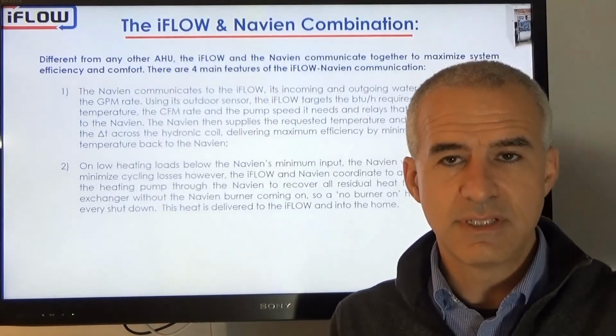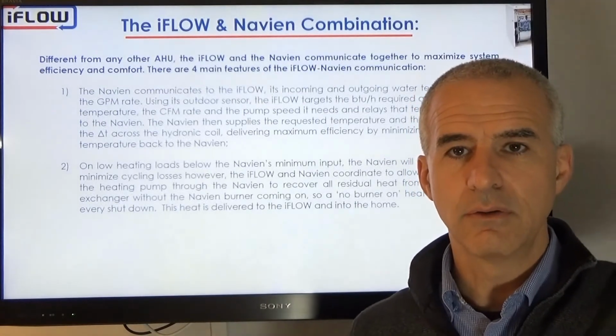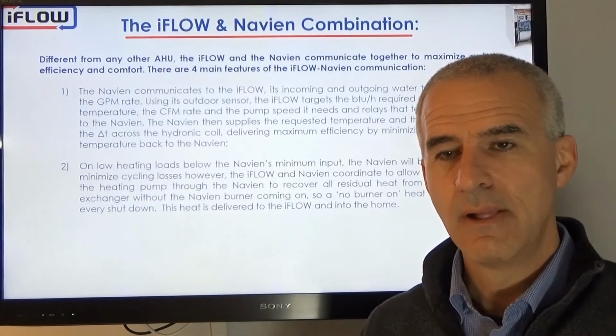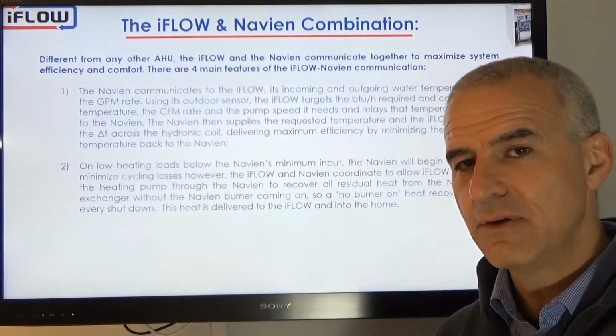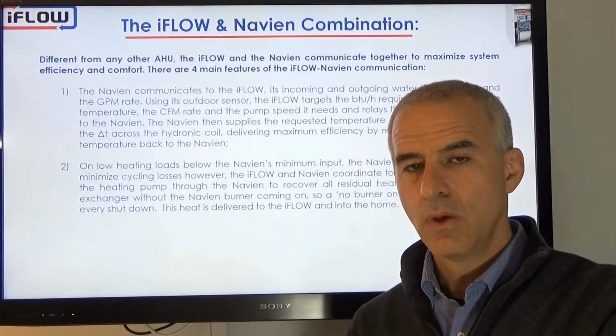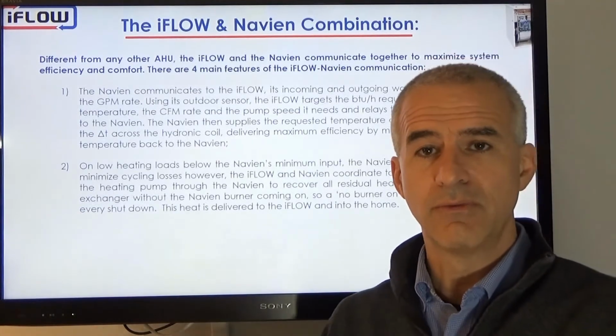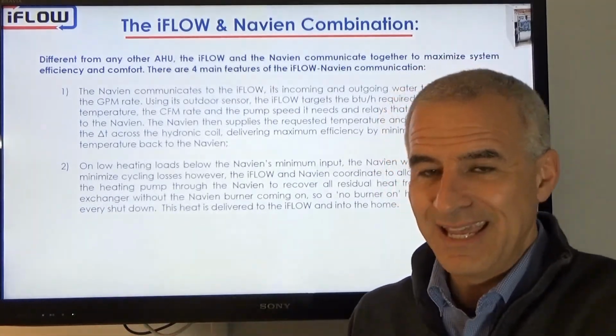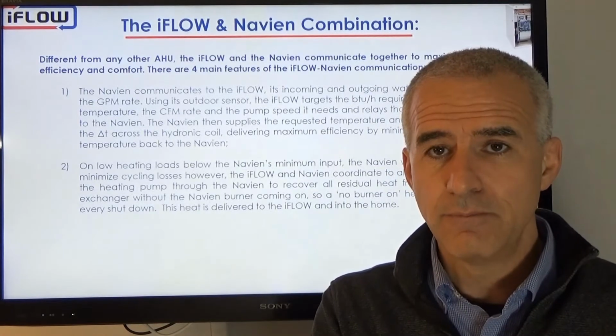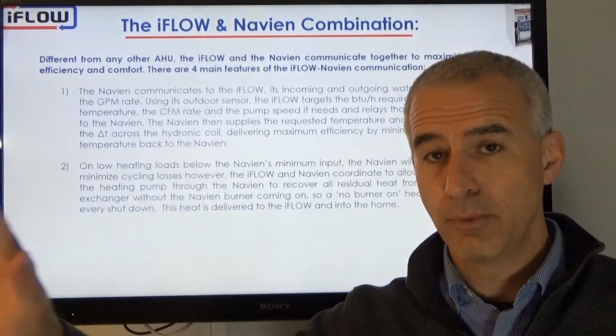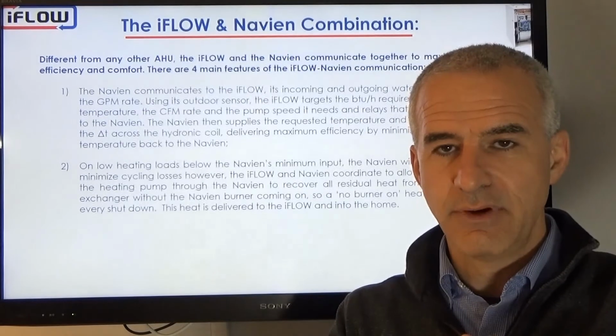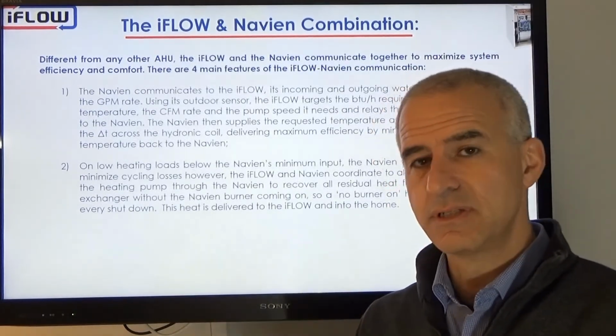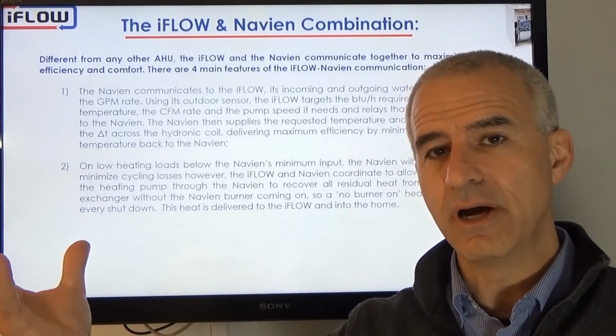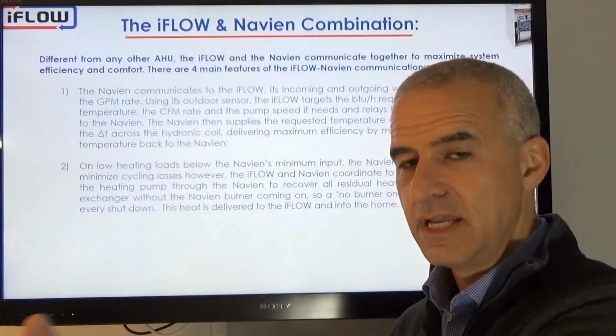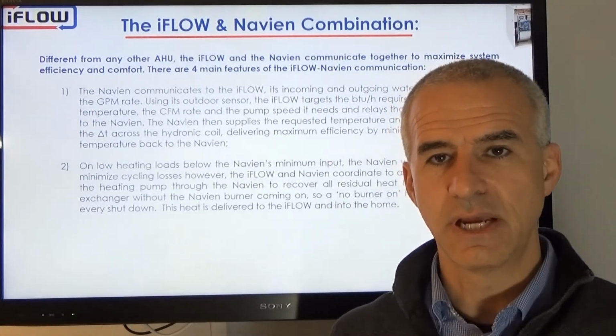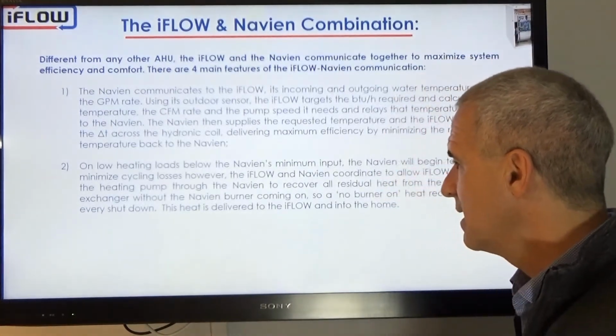So we keep the CFM running through the iFLOW, the airflow through the iFLOW delivering into the house, but we scrub all the heat out. So even when the Navien is cycling, we're not wasting all of that heat like we would with the furnace. We're actually recovering it, bringing it into the iFLOW, because we're keeping the pump running, but with the burner off, and then delivering it into the house. And as soon as the temperature is such where the Navien burner can fire up again, it will fire up, start heating the water again, and continue the cycle.